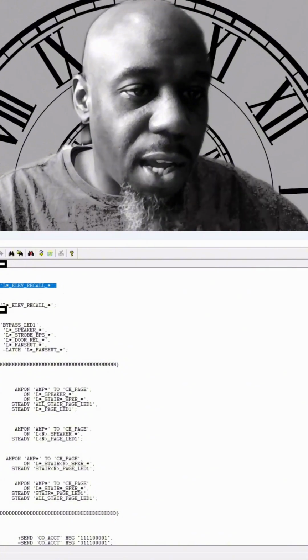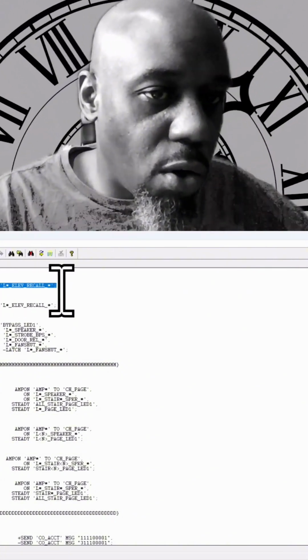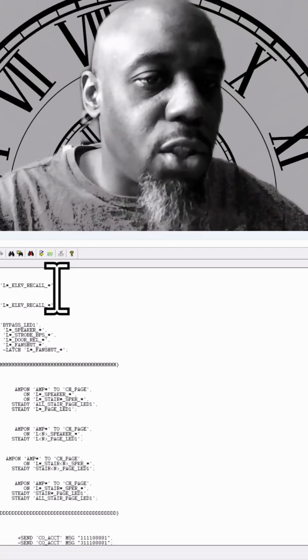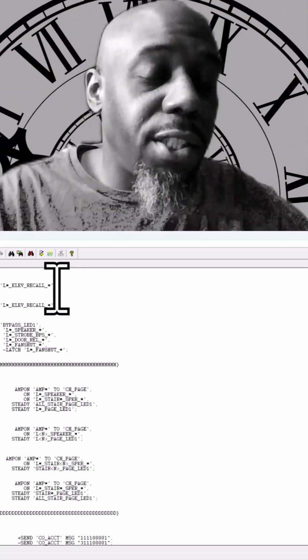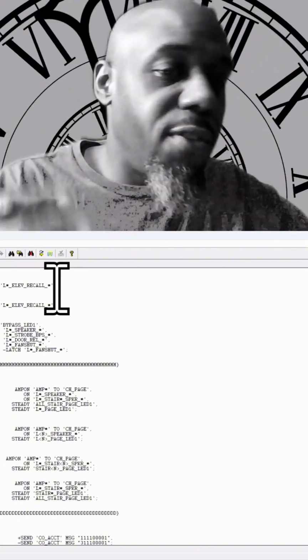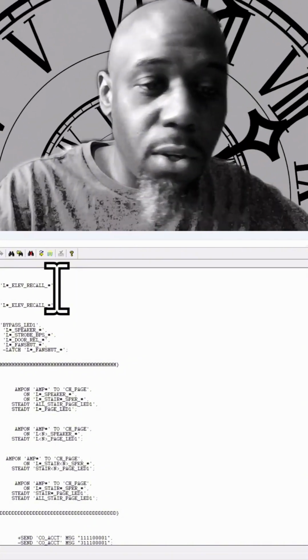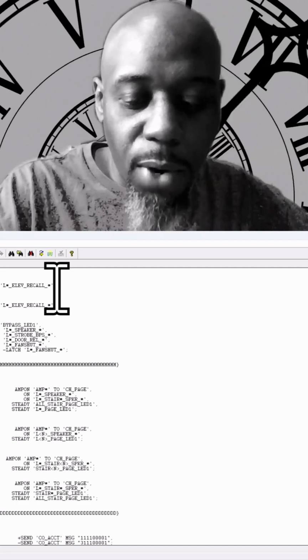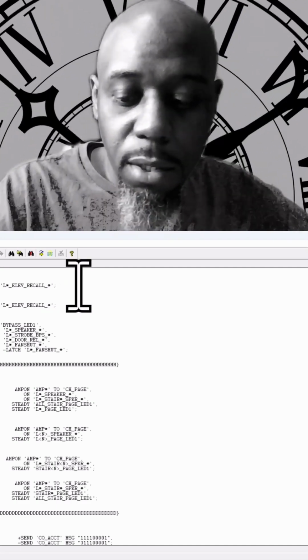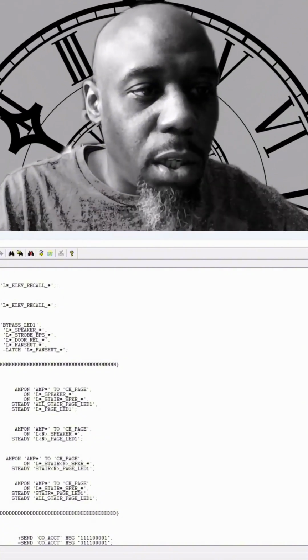Now on the output side, they're turning on a relay. It's an elevator recall relay, and they have a semicolon to end the rule equation. If you don't have a semicolon at the end, it's going to say that you have a syntax error. When you try to compile it, you're going to get a rule error. Let me show you what that means. I'm going to erase that and put just a regular colon, and we're going to save that, and then I'm going to close this.